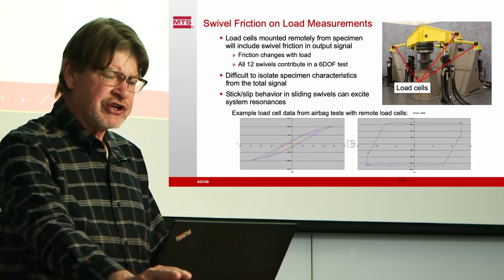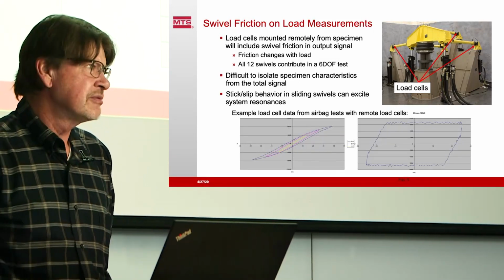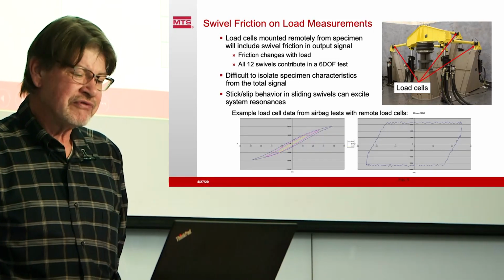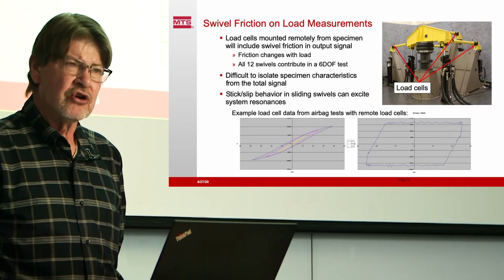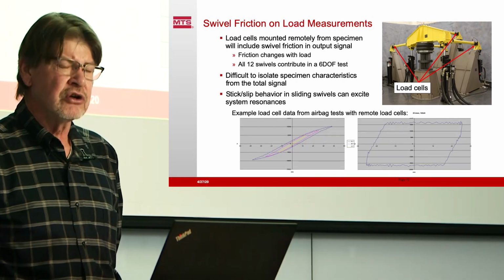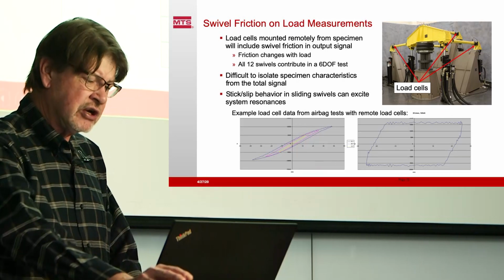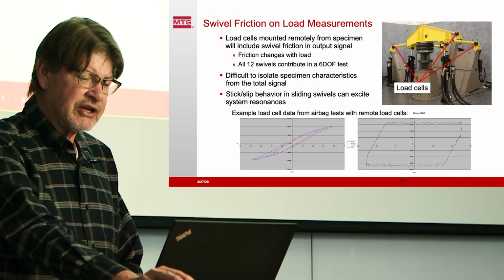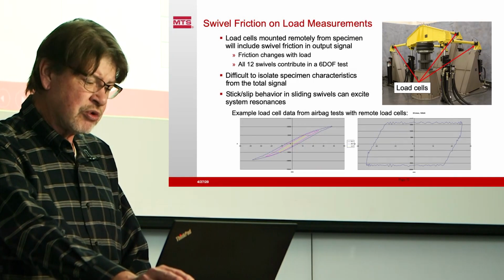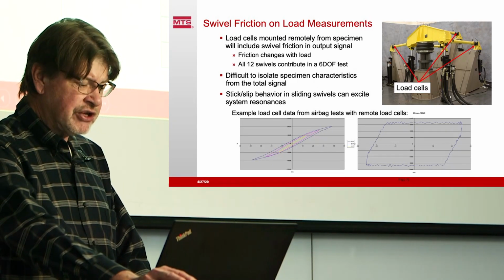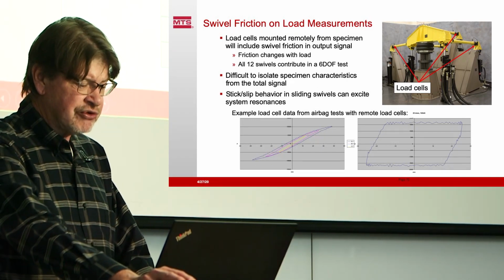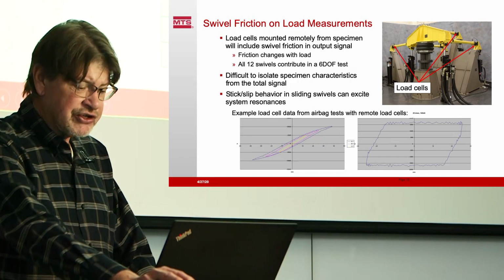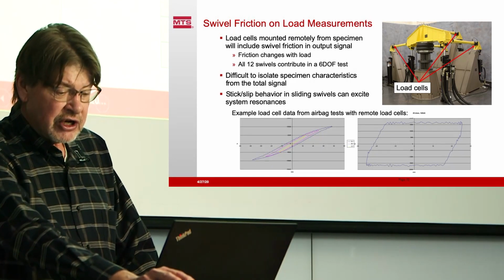So swivel friction is another source of error in load measurements. If we've got swivels in our load train, we will have friction in our load cell readings. You see some examples here. This was a multi-axial airbag test, so we preload it and then we swivel it around. And you can see here with different preloads, we get increased hysteresis in the bearings and quite a significant level of friction from these bearings.